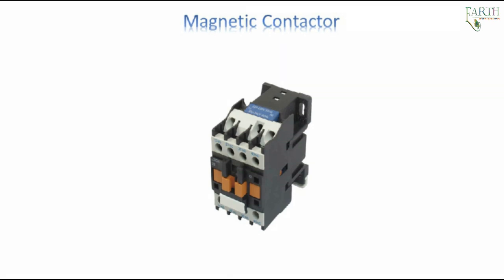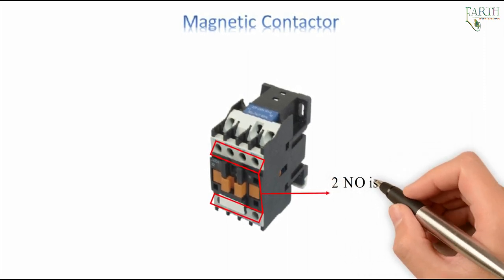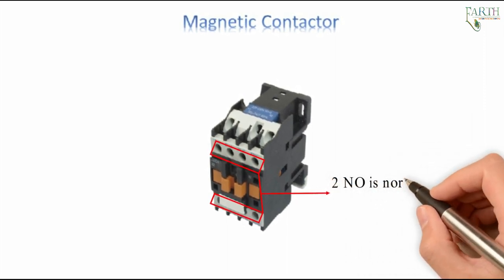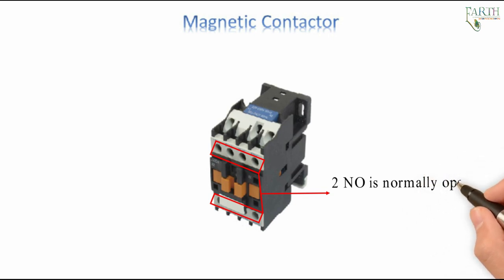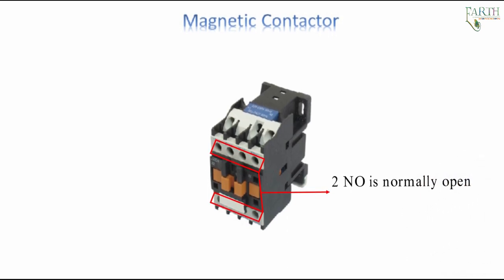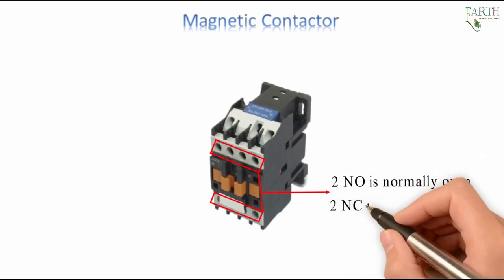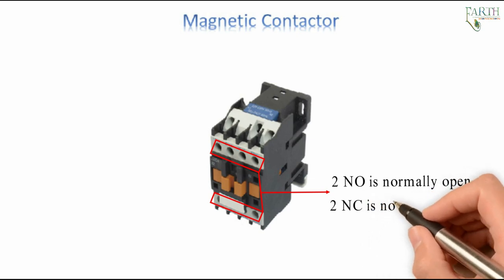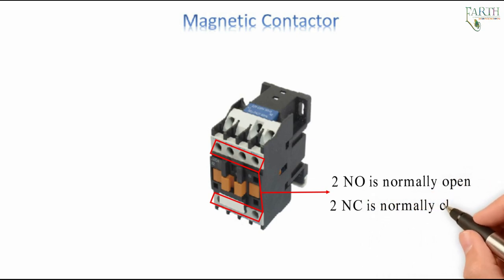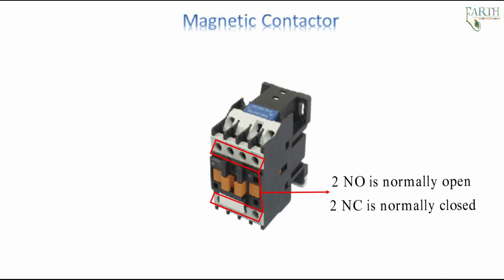It also has a set of auxiliary contacts. Generally, 2NO (normally open) means the contacts are not closed and close when the switch is actuated. 2NC (normally closed) means the contacts are normally closed and open when the switch is actuated. 2NO and 2NC are used for control wiring.